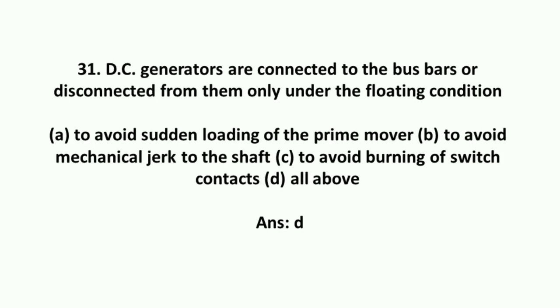DC generators are connected to the bus bars or disconnected from them only under the floating conditions to avoid sudden loading of the prime mover, to avoid mechanical jerk to the shaft, and to avoid burning of switch contacts.